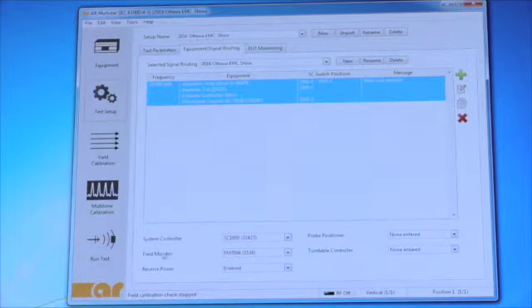So once you have that all set up, you have your system controller. You select here your field monitor, and you enable reverse power. We have 2 systems that actually measure just forward power, and then the other one is measuring the net power, so it needs forward and reverse power. If you have a positioner, you can enter that, or a turntable controller.